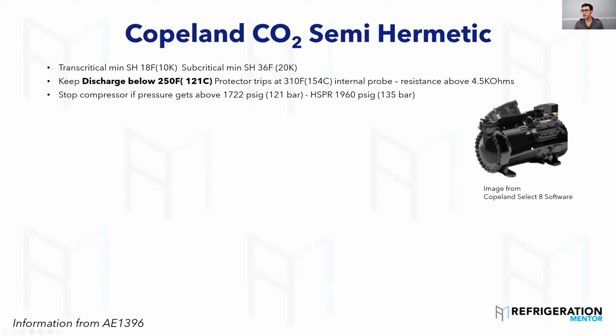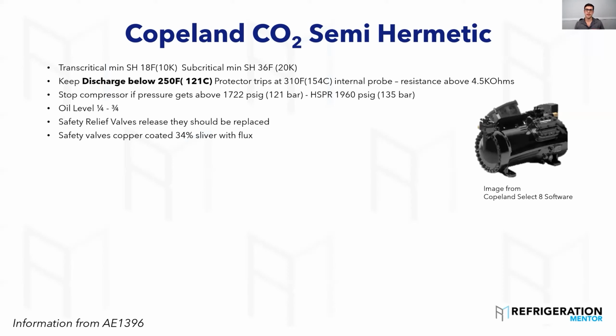There's one right here. There's two of them on this one. The discharge one will be 1960. If these reliefs open, they need to be replaced. And it doesn't matter what compressor manufacturer, that's what they say. Oil level, quarter to 3/4. Bitzer says the same thing, quarter to 3/4. Safety relief valve should be replaced, like I mentioned.